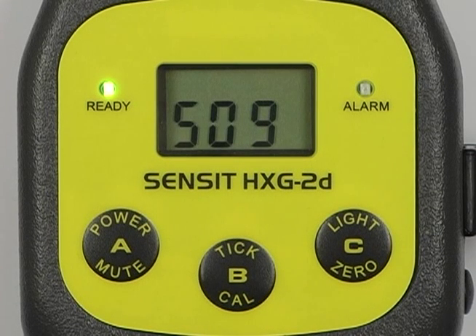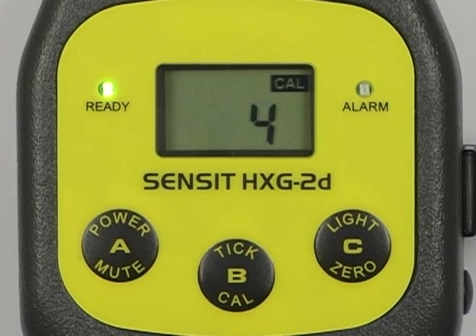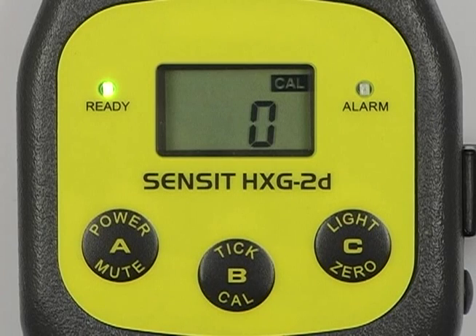A BAD calibration will be indicated by a beep followed by BAD being displayed on the screen. If the instrument does display BAD after performing calibration, the unit may require the LEL sensor to be replaced.